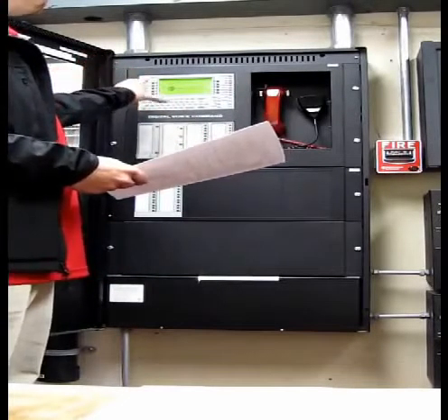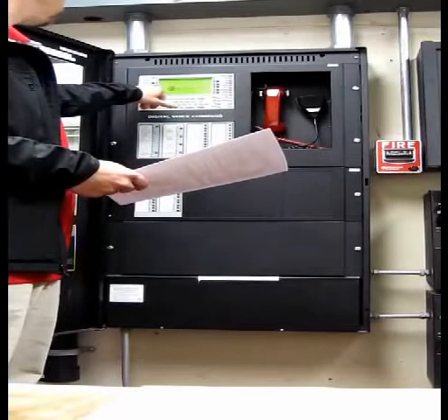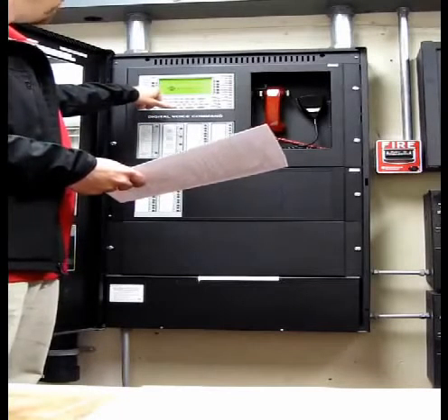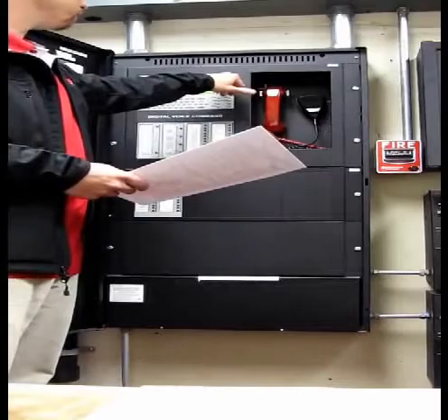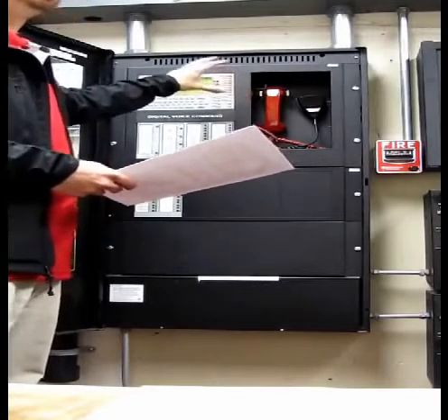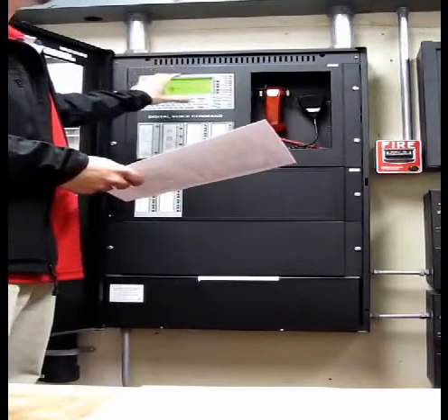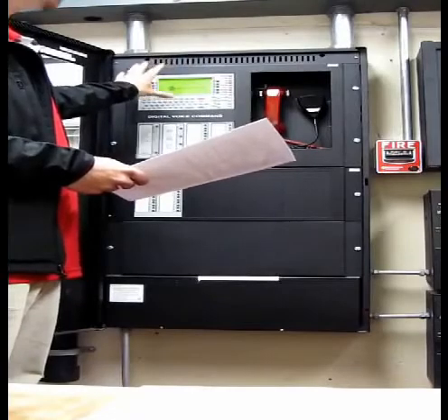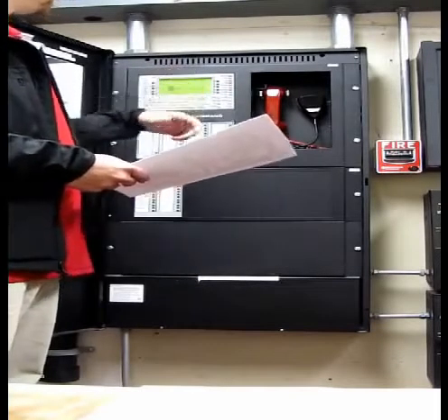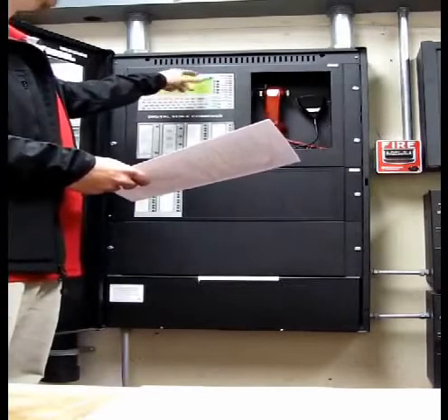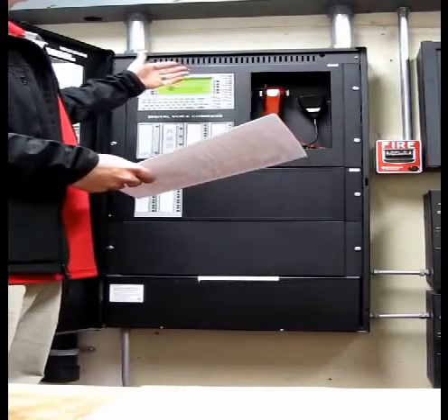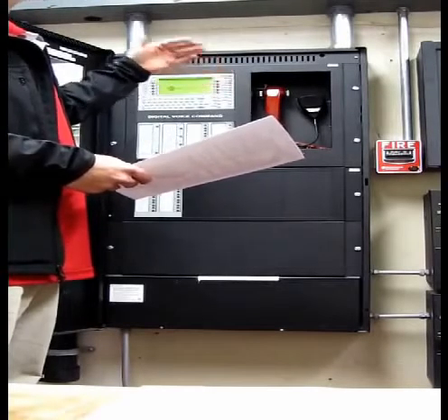What's going to happen on the panel is it's going to beep. You're going to have the system trouble light come on right here. And the only thing you can do at that point is hit the acknowledge button. Acknowledge basically is just acknowledging that you know there's something wrong with the system, and it silences the local piezo within the 3030 here. So you'll have a display on here too of what's wrong. It'll say, for example, device missing. It'll say no answer, loop 1, device 65.